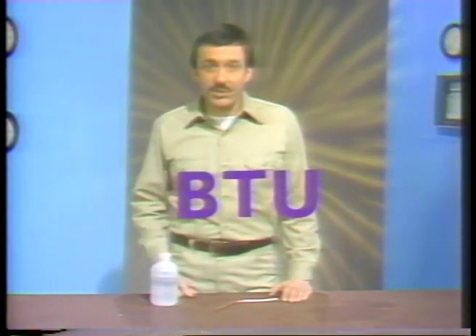The common units for heat are British thermal units, which are abbreviated BTUs. A BTU is defined as the amount of heat required to raise the temperature of 1 pound of water by 1 degree Fahrenheit. In order to calculate the actual amount of heat required to raise the temperature of a certain amount of material, we must take into account the fact that the amount of temperature increase for a given amount of heat is not the same for all materials.